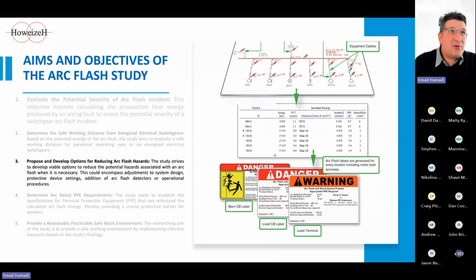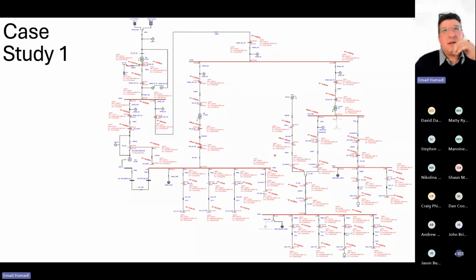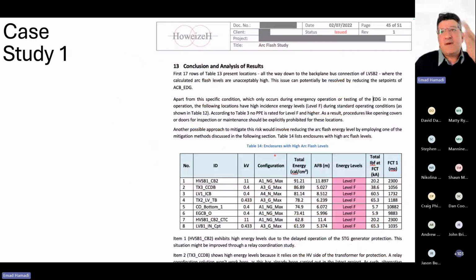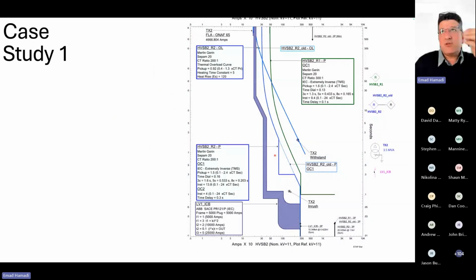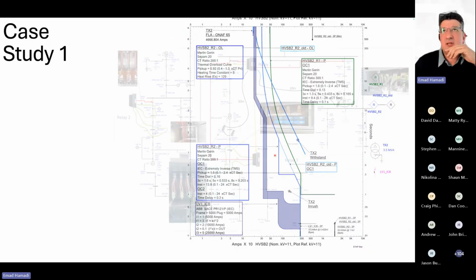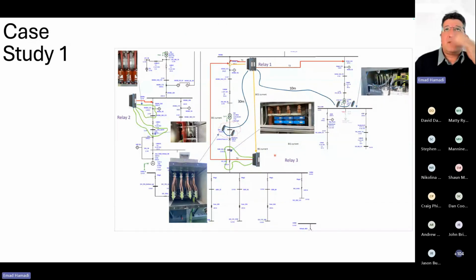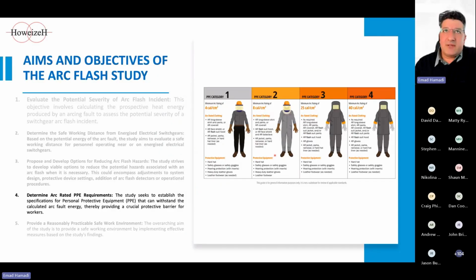So proposing and developing solutions for reducing arc flash hazard is one of the outcomes of the arc flash study. Here is a case study: the site requested us to assess the arc flash, and we identified different locations with a high energy level. Then we proposed a few measures. One of them was fine-tuning the protection settings, which overcame the issue and reduced the energy in some locations. For those locations where it was not possible to reduce the incident energy by the relay settings, we installed arc flash relays, and we ended up with a system which is safe and sound from that perspective.